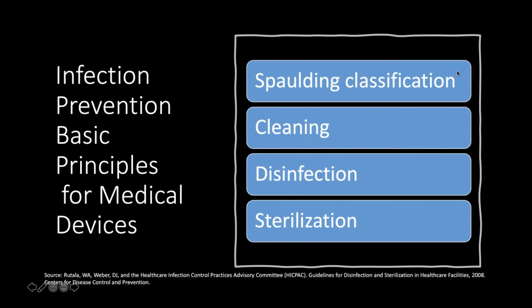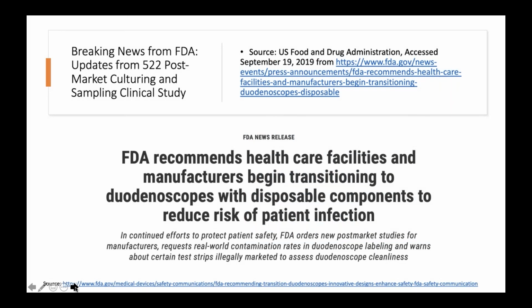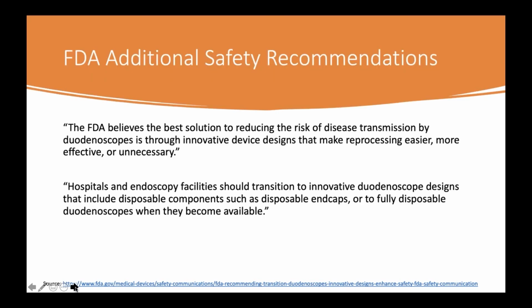But again, you're seeing a lot of movement in the clinical societies and in the peer-reviewed literature to think about flexible endoscopes not as semi-critical, but really to move it up a notch because of the known associated risk of infection. So the FDA said, hey, we've got a problem here, right? We've got data that suggests this is bad. We've got adverse events that say we've got a problem. We've got lawsuits out there. And so they put out a safety alert that basically said we need to look at transitioning to duodenoscopes with disposable components. And then they took that a step further and drilled down a little deeper into what is really the best possible solution long term.